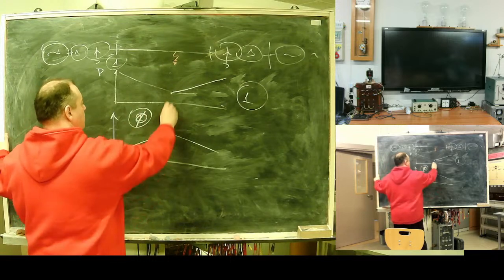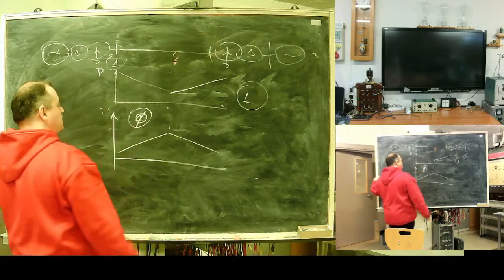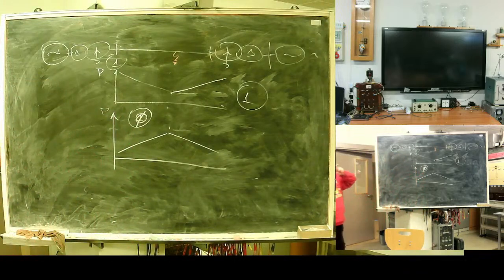This is zero, let's say active power and zero sequence. It's powered from the fault place. So, meaning that the closer the fault place is towards the relay, the higher power the relay will see. That means there is virtually no sensitivity problem with the close fault. Sensitivity problem goes this far from relay, when my protection operates as a backup.